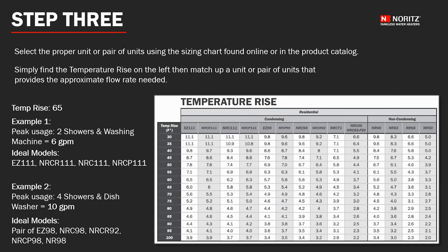The third and final step is to select the proper unit or pair of units using the sizing chart found online or in our product catalog. Simply find the temperature rise on the left and match up a unit or pair of units that provide the approximate flow rate needed. Since we determined our temperature rise was 65 and a peak flow of 6 gallons per minute for example 1, we can see that any of the 111 series provides 6 or just about 6 gallons per minute and would be a great choice.